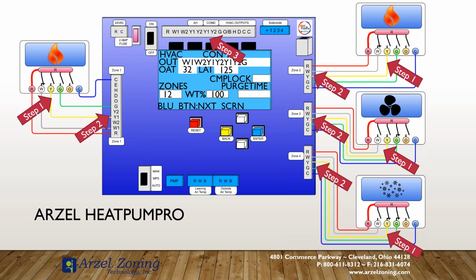And then the zone panel tells us exactly what it's outputting for. And those outputs are a thermostat in relationship to our equipment. So we don't have to try and diagnose all 4 zones in our equipment at the same time. We can break each zone down individually, and then we can break the equipment down away from the zone thermostats themselves. So rather than turning a thermostat on saying the equipment's not working and then instantly condemning the Arzel board, we need to take a look and verify that the thermostat's doing what it says it's doing, and then see what the panel says it's doing and verify that as well.